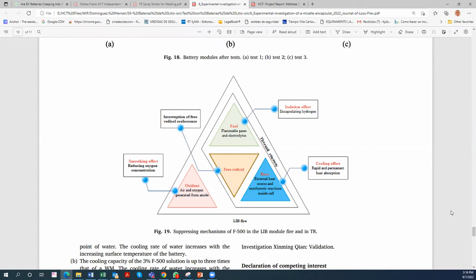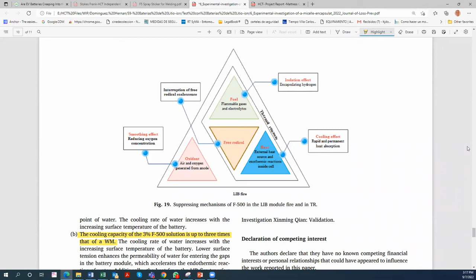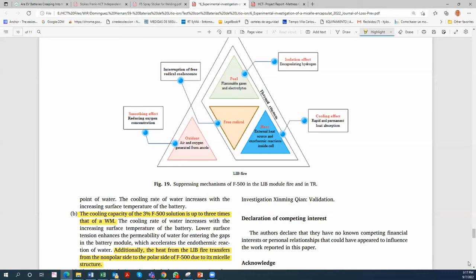One of the conclusions here is that the cooling capacity of the 3% F500 solution was up to 3 times greater than that of water mist. Why is that? Well, with water mist you have smaller droplets, but your heat reduction is still steam conversion, and steam conversion is not very effective. As Jeff mentioned, this encapsulator agent changes the heat reduction mechanism of every droplet. We go from steam conversion to a term we call thermal conveyance, conveying the heat through the F500 molecules and around the spherical micelles inside every droplet.